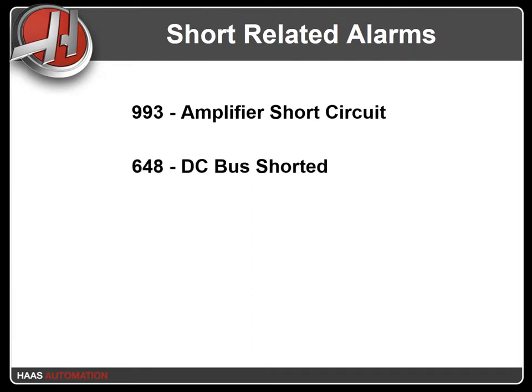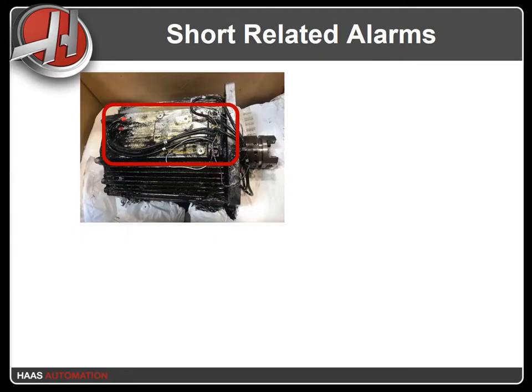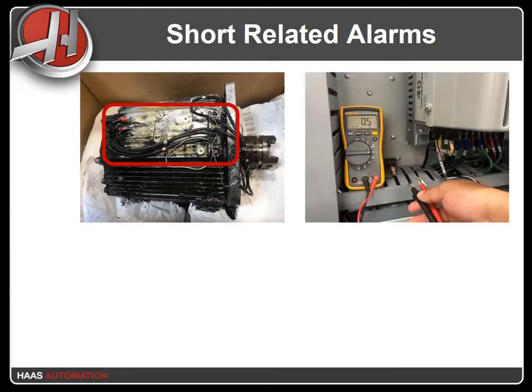Shorted cables, a shorted motor, or a coolant-contaminated motor can cause a short across the drive's outputs. A shorted regen load or shorted amplifier can also cause the drive to react. The drive protects itself during all of these conditions by generating any of the following alarms: Alarm 993 amplifier short circuit, Alarm 648 DC bus shorted, or Alarm 647 regen load shorted. When any of these alarms is displayed, the drive will stop all outputs to the spindle motor. The first thing to do for a short circuit related alarm is to inspect the motor and make sure that it's not shorted.